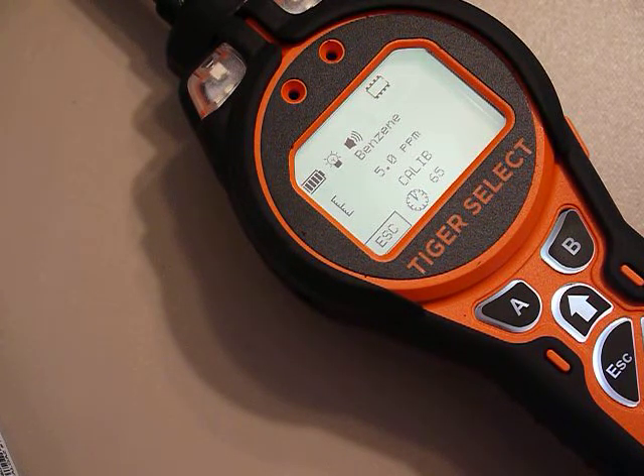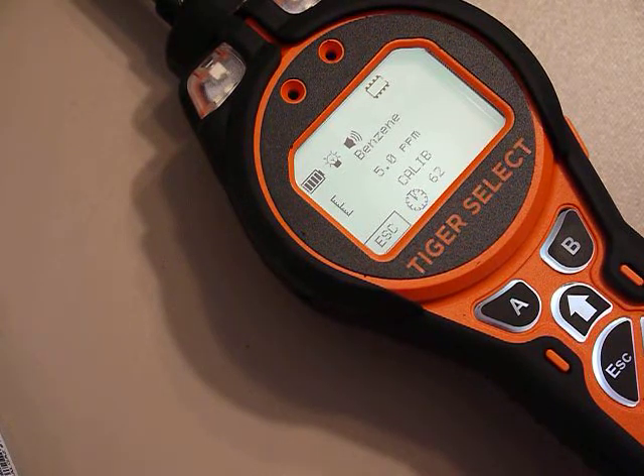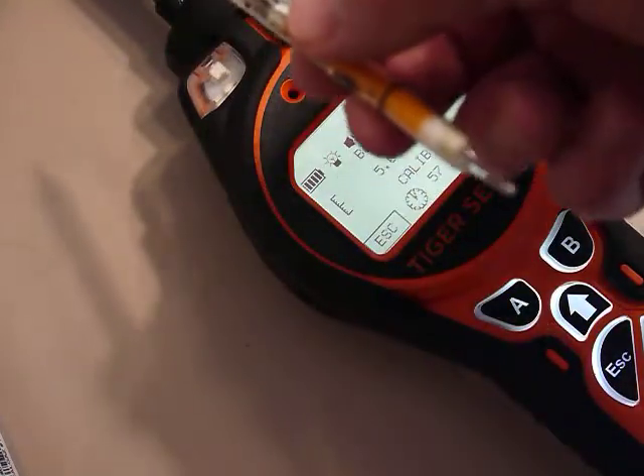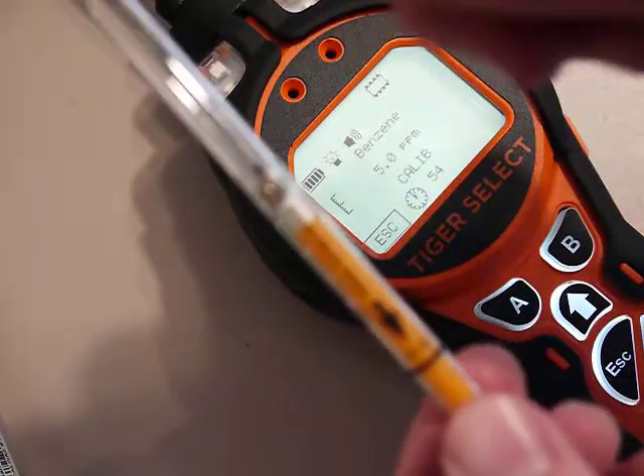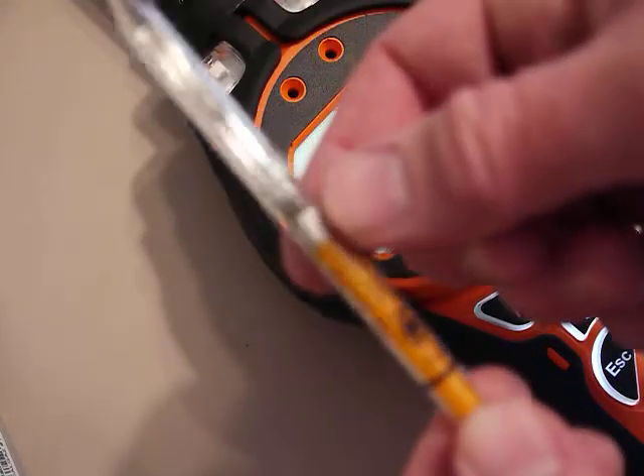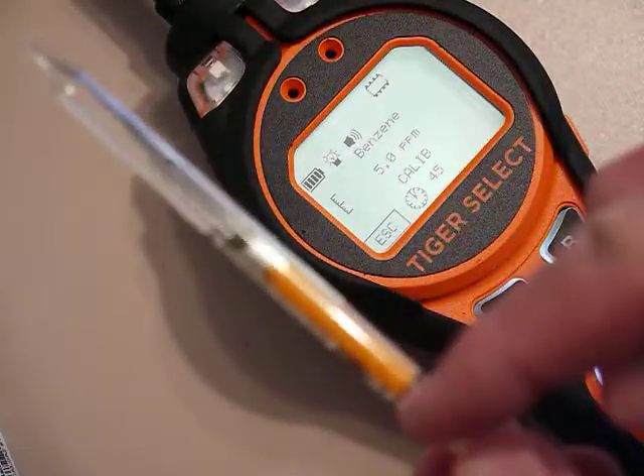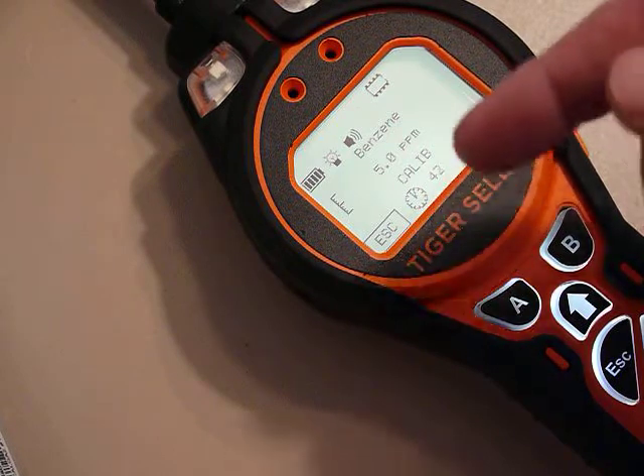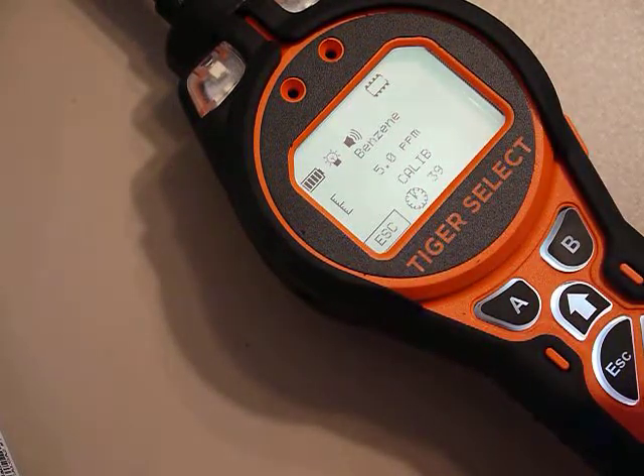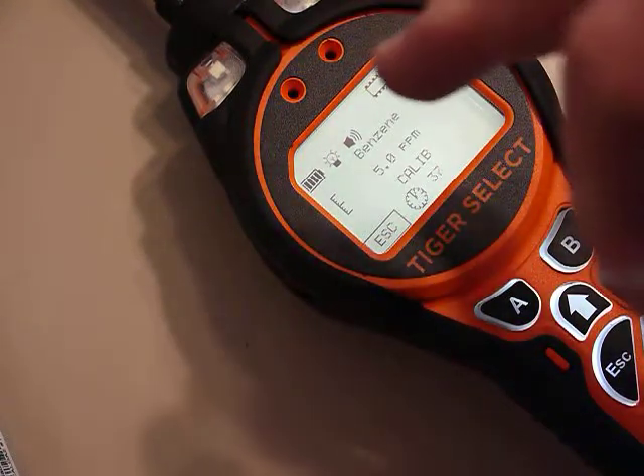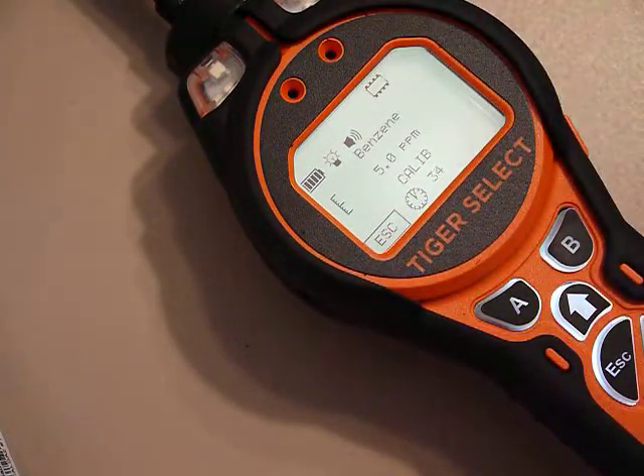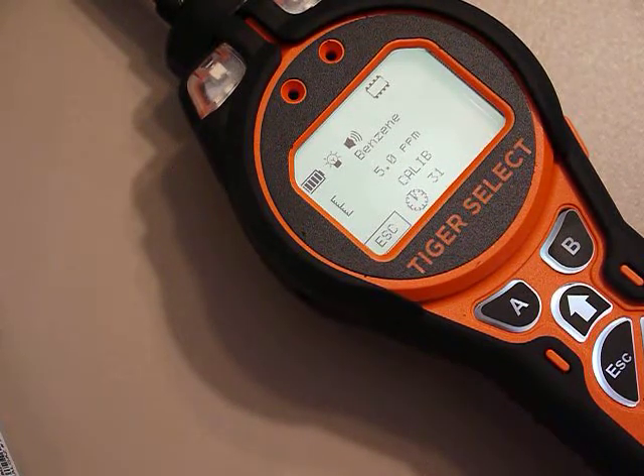So the meter's trying to get a steady reading on the gas, basically. Now there's a tube in the sampling end here, but basically what's happening is as the gas comes through, there could be lots of other VOCs in there, they all get scrubbed out, and the only thing that makes it through this tube is benzene, and the meter knows a correlation factor for benzene, so it basically gives you a measurement directly. So this is a calibration to the tubes. There'll be another video to show you how to actually take a sample and do the benzene measurement, but this is setting up for calibration with the tube. So we still have about 25 seconds.